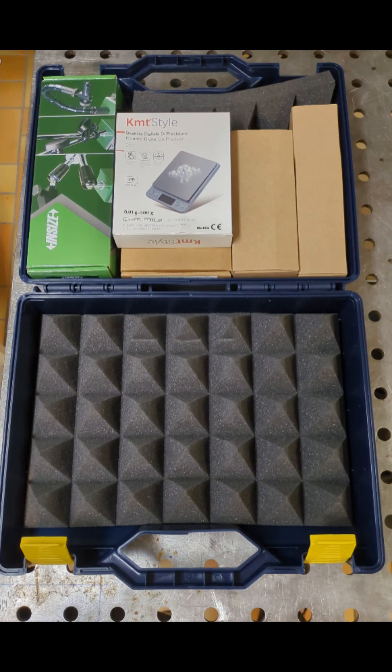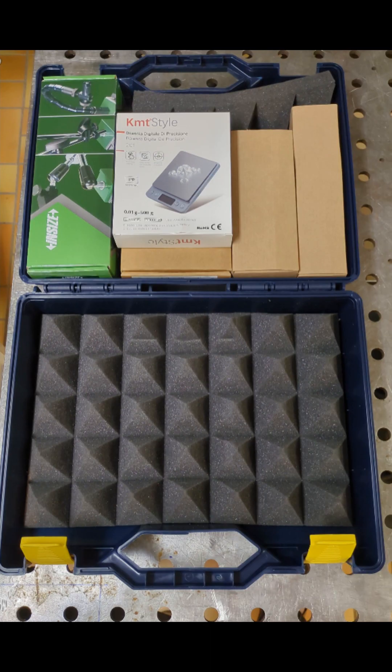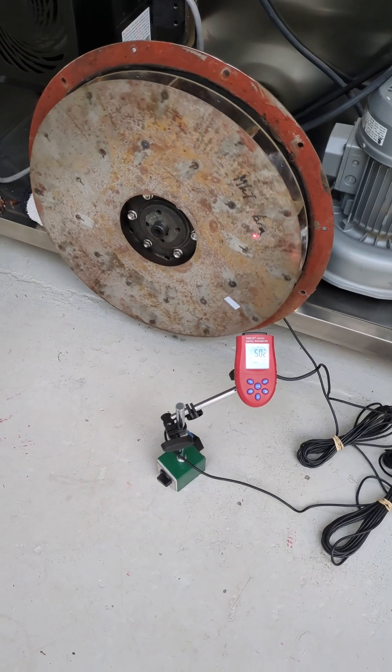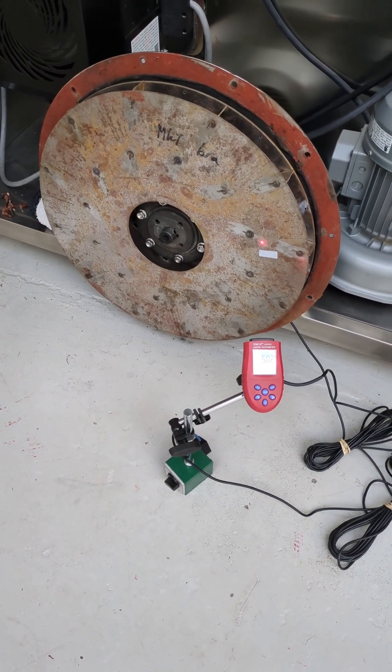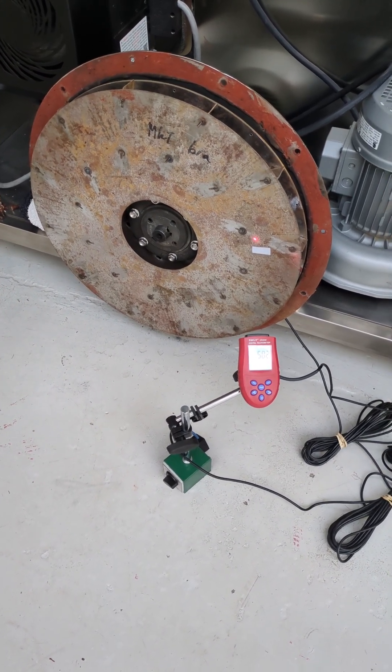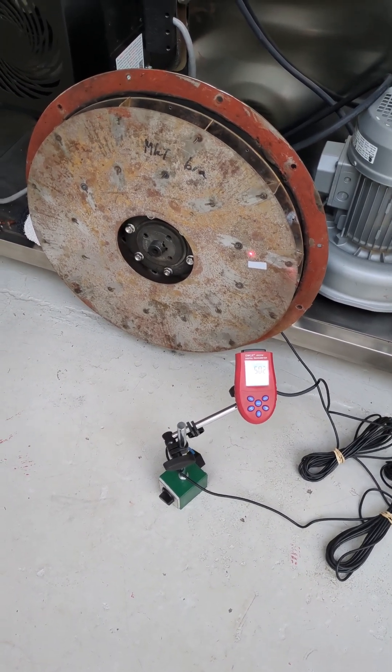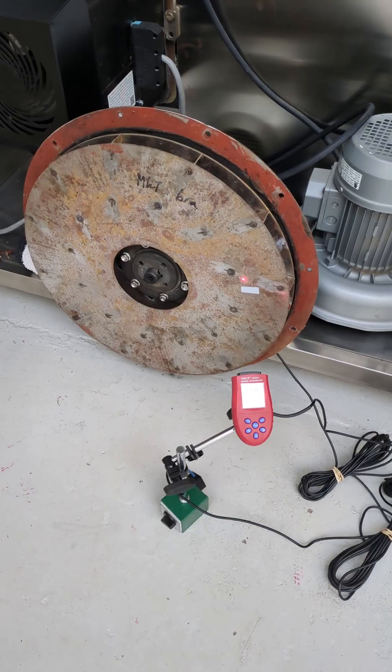And from the trial weight position then move the degrees indicated and in our case remove material. The two plane dynamic balancing works fantastic. Now Vibromera is a field kit. It's supposed to be used in the field. So let's move over to the field.